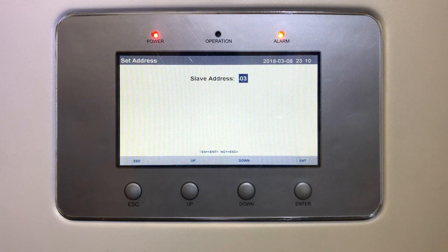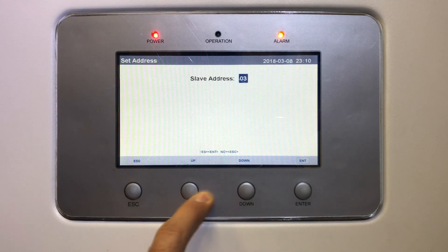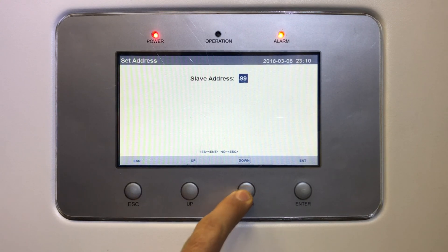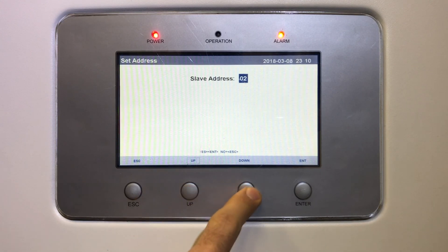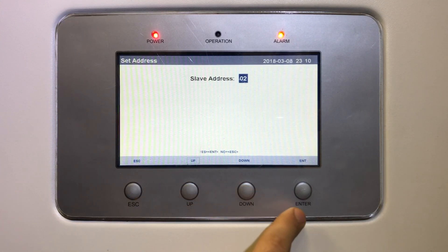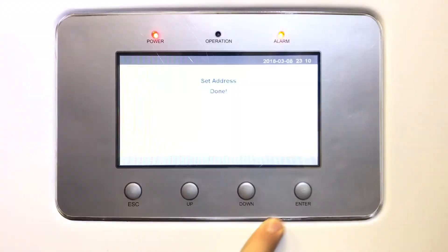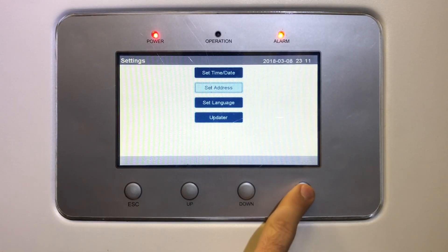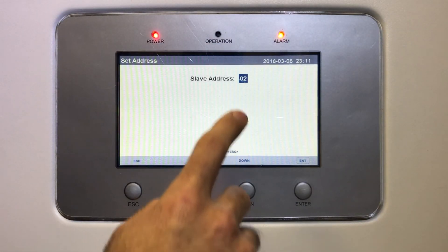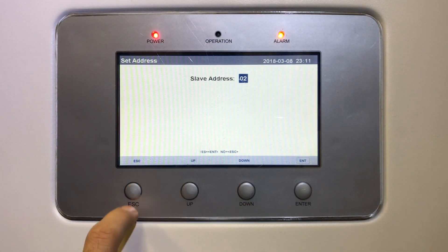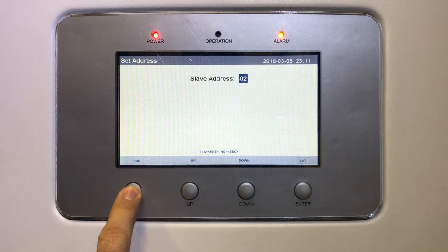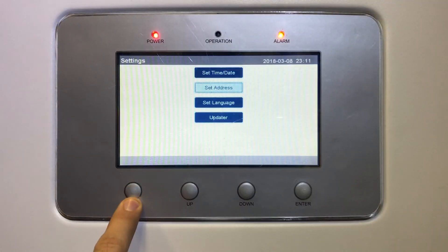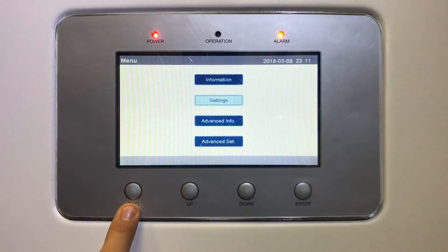From here we can change the inverter slave address to match how it is defined in the single line drawing. Use the UP and DOWN buttons to choose the correct number between 1 and 99. For this inverter, the single line drawing specifies slave address 2. Press ENTER to submit the value. To make sure that the value is properly submitted, we can hit ENTER to go back to the SET ADDRESS screen, where we can see that the value is still 2. Now we can hit ESC to exit without changing the value, and hit ESC two more times to get back to the GENERAL OVERVIEW screen.